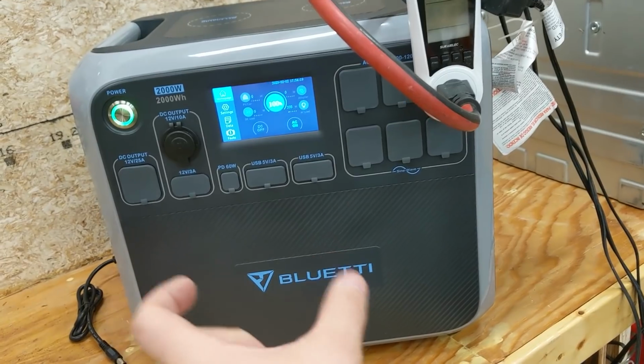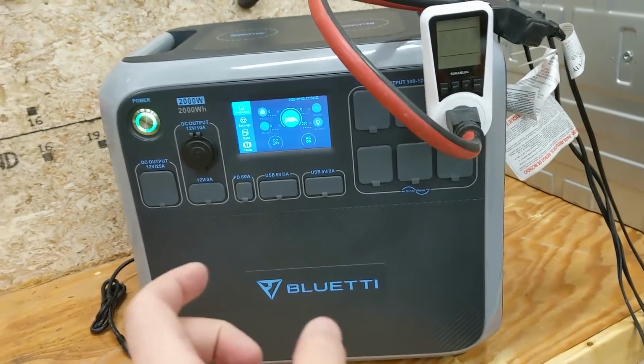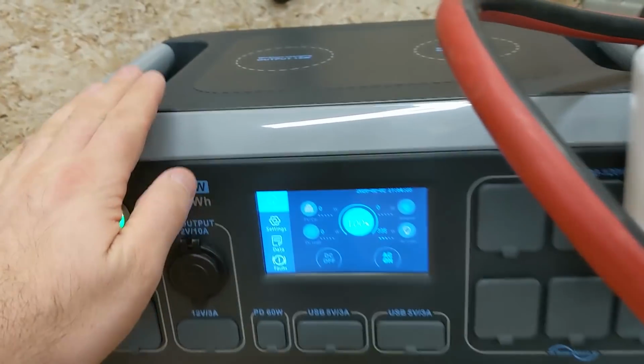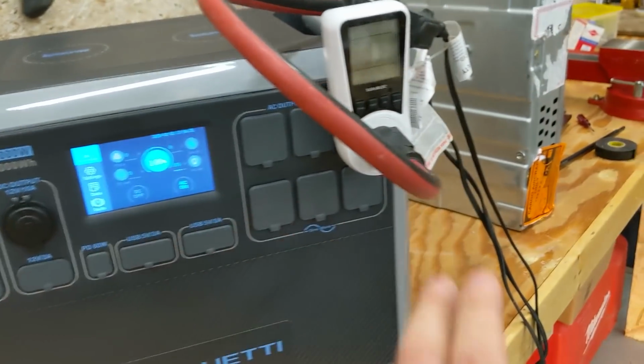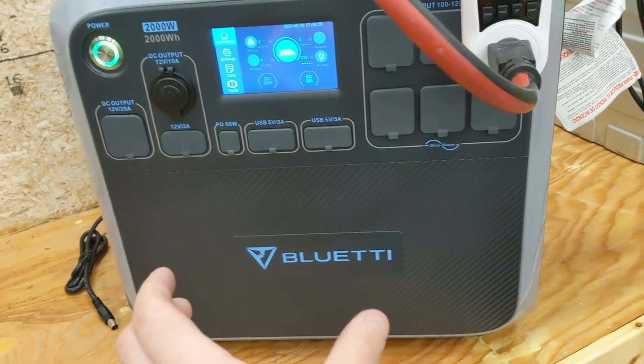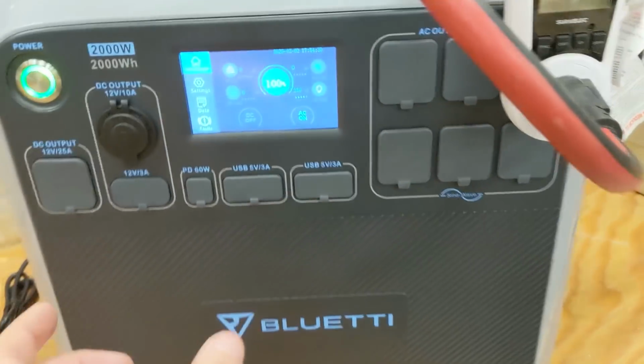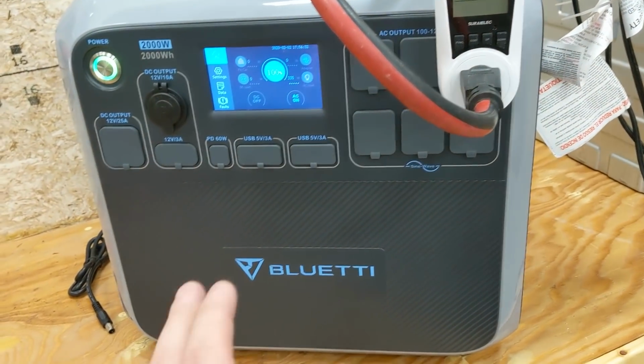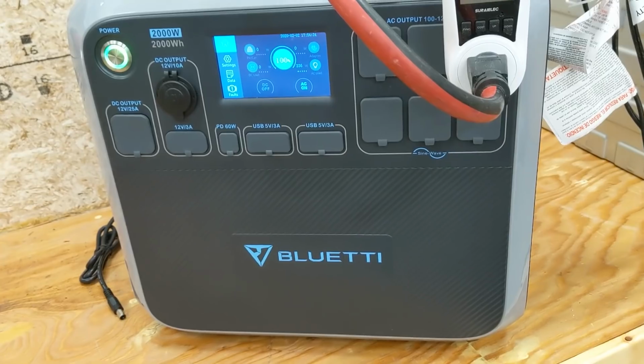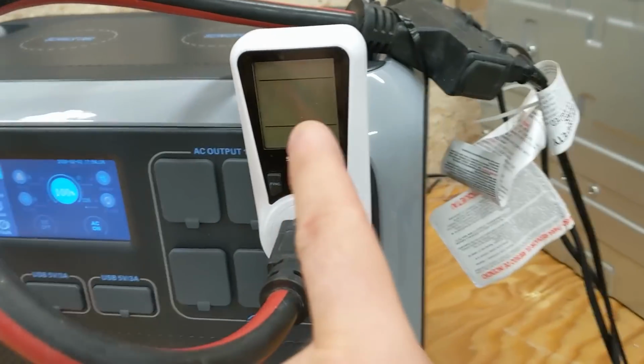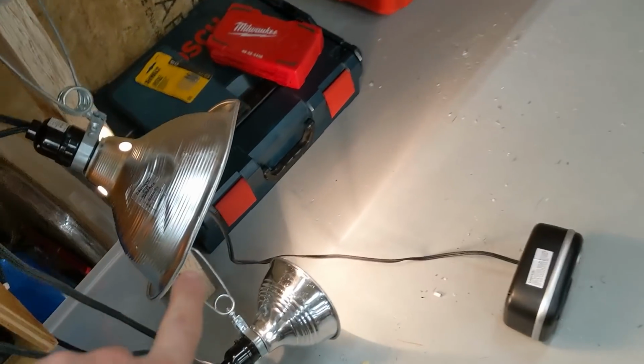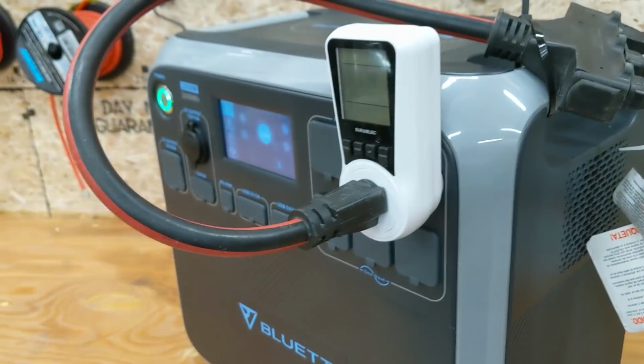Ideally you want a 5-hour discharge on the battery. Now I don't know exactly how efficient the inverter is going to be with this exact load, and I don't know at what parameters the BMS kicks on and off. There's probably some amount remaining. So having this at 350 watt discharge, that's with 2 light bulbs and the heater, that should be about right.